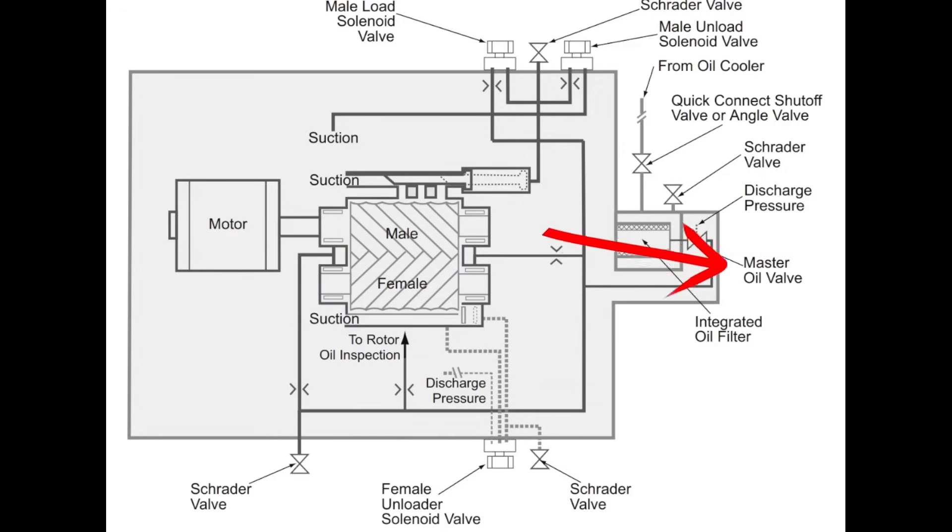All these extra lines and stuff through here is part of your oil circuit. So what the female unloader is doing is it is opening this bypass and allowing discharge gas to be rerouted back into the suction gas. What that allows us to do is have an unloaded start beyond what the slide valve can do.